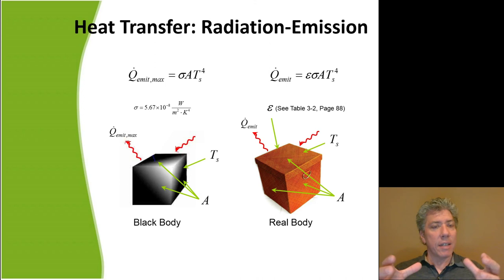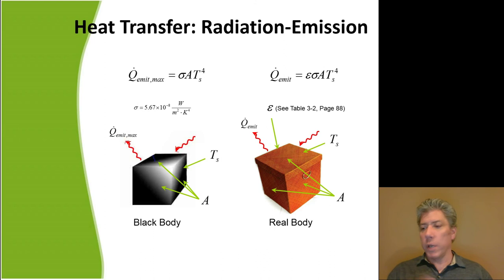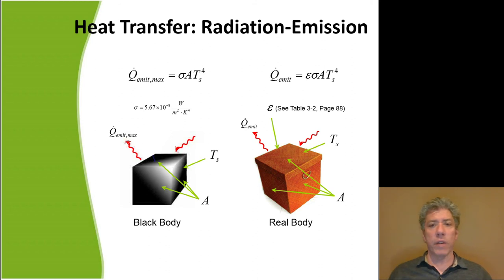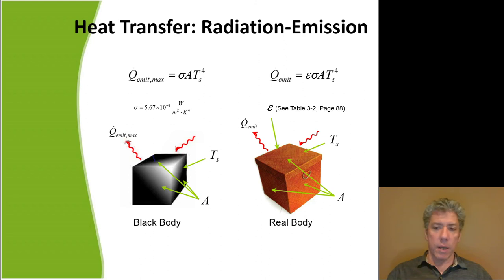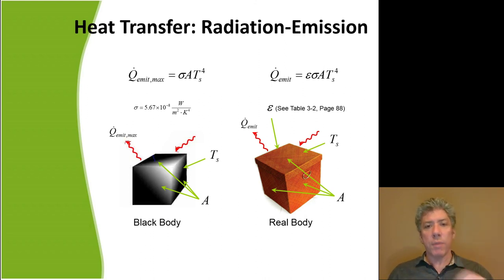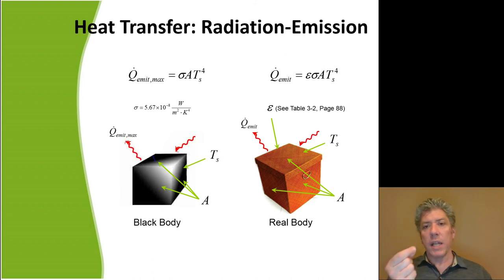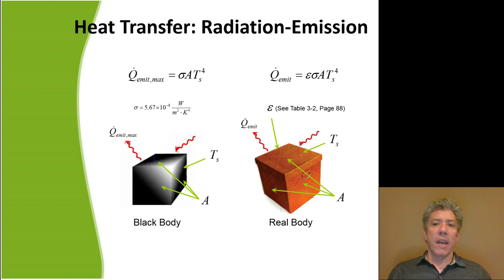When I pointed my infrared thermometer at this galvanized pipe, I measured a temperature of about 40 degrees. I thought there's no way that's right — from my thermocouple inside the pipe I knew the exhaust gas was at about 400-500 degrees. A single wall of very thin metal has to be at a higher temperature. I threw some water on it and sure enough the water boiled, so I knew the surface temperature was very high and my thermometer was not measuring properly.